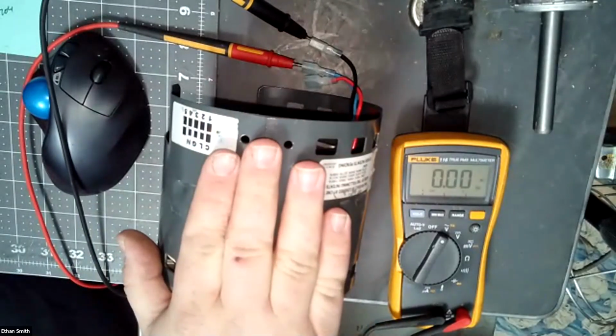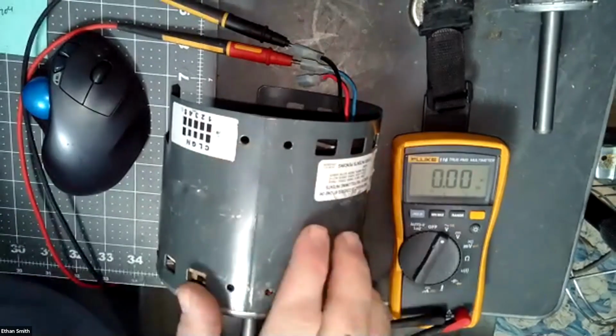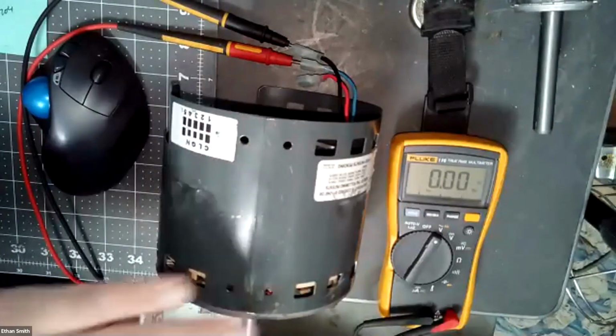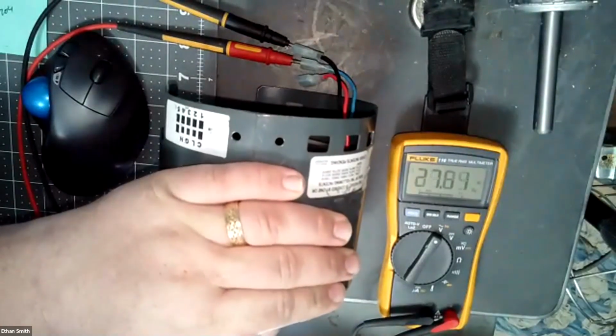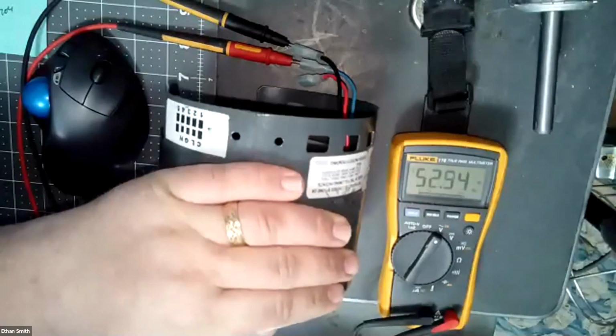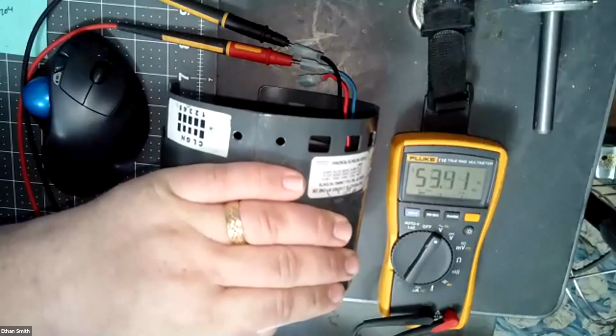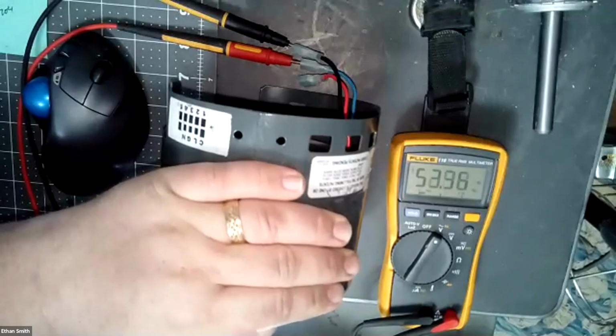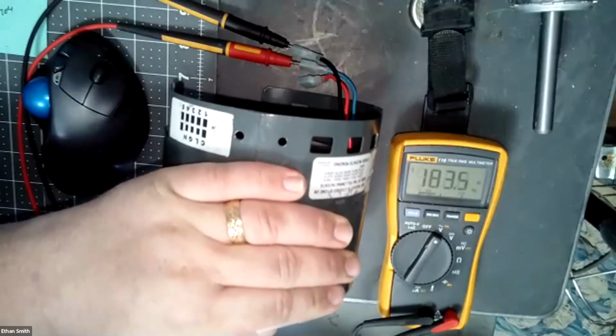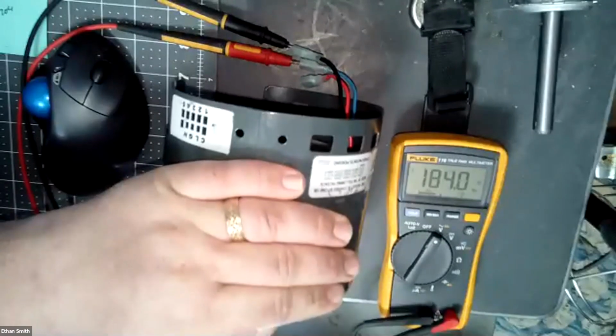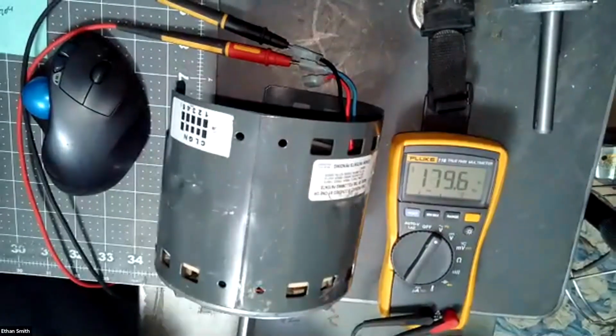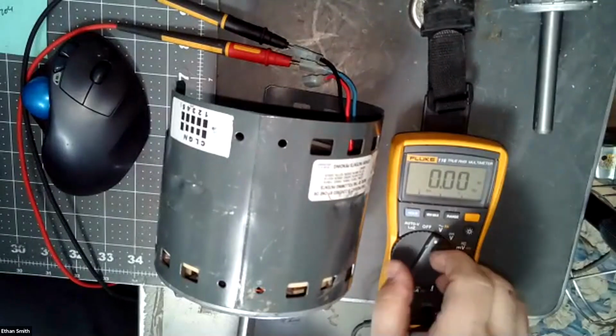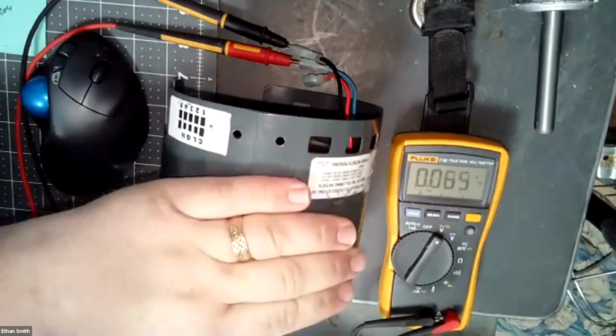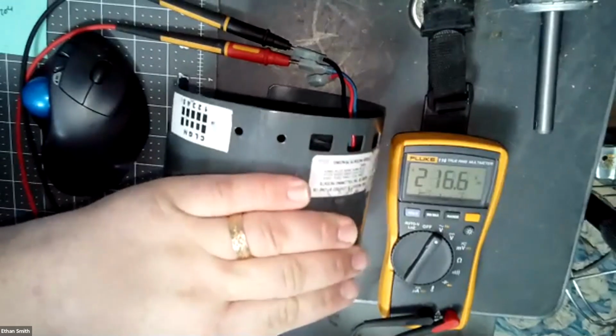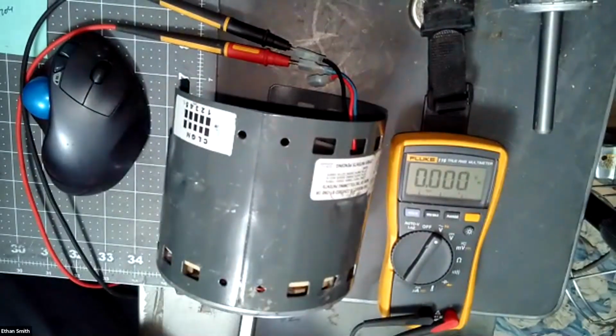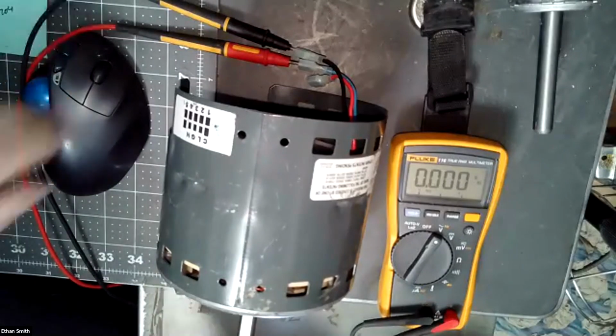I'd get 60 Hertz. Okay. So I've switched my meter over to frequency, and what you'll notice is that I'm at about half speed and I'm running 60 Hertz. If I go to full speed, this thing tops out around 180 Hertz. Okay. And at 180 Hertz, I'm doing 220 volts.